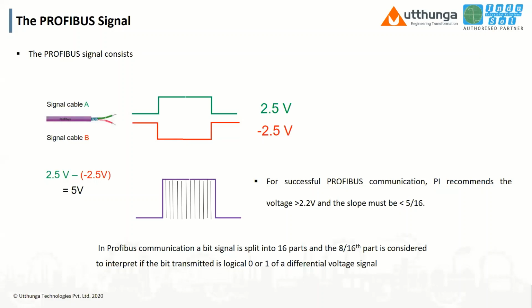The Profibus signal has two wires, mainly green and red, as you have seen in the commissioning part. You have 2.5 and minus 2.5, adding up to give the 5 volt communication. And each signal is divided into 16 parts. How it interprets the 0 to 1 transmission is shown here clearly.